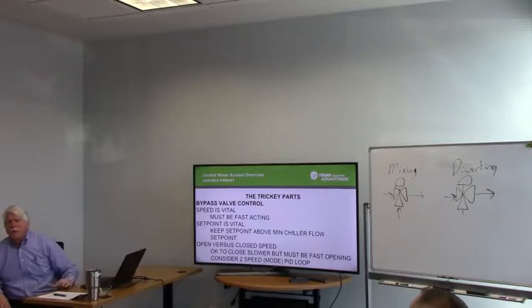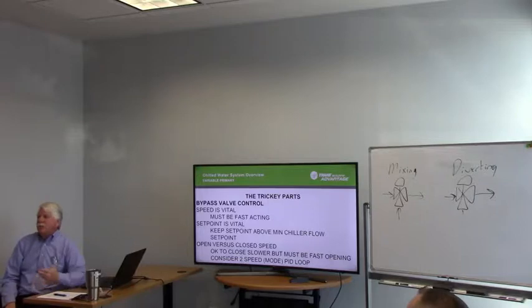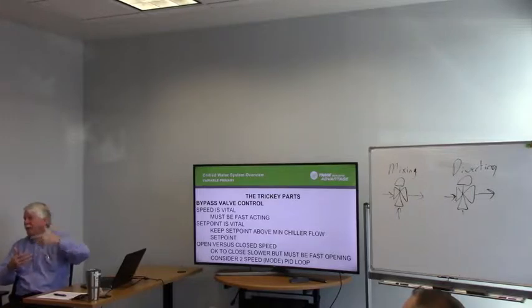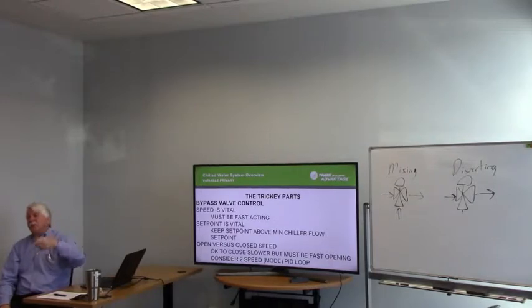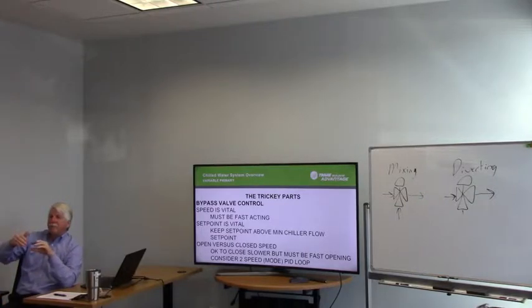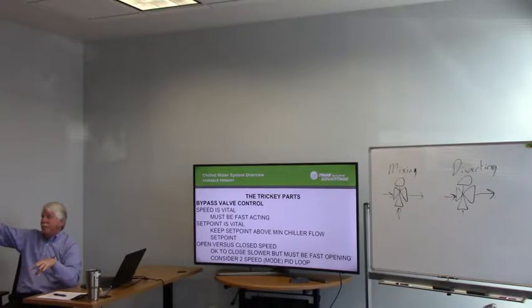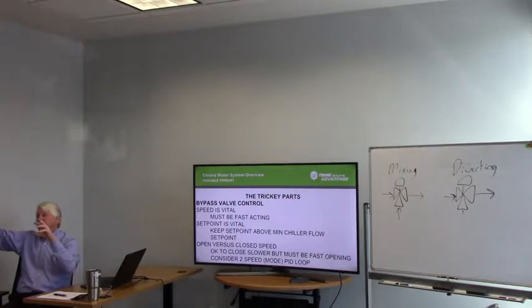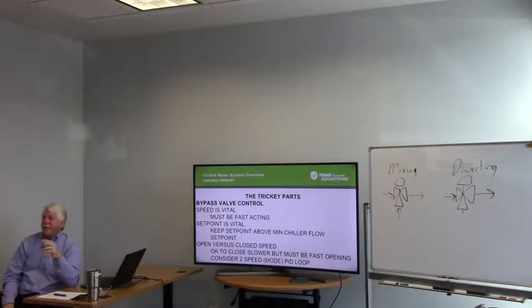Are most of you guys familiar with adjusting the P with some logic on your DDC loops? Usually you have a constant that's your P that you'll bring out as an AV or something like that. But what I've done on jobs that are really critical is I'll take that value and run it through a logic block down at the PID loop. And I'll say, if the pressure right now is below set point, I'll take that value and multiply it by 2. I want this loop to act twice as fast if the pressure gets below set point. And then if the pressure gets above set point, I remove it and it works on the normal one. But that's one of the ways you can kind of force a loop to act at different speeds in different modes.